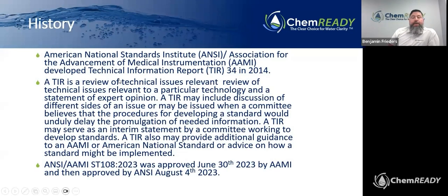So the history behind AAMI ST108 is ANSI and AAMI developed a technical information report, TIR 34, back in 2014. So this report and this information has been out for about 10 years. Here at GetChemREADY, we've been aware of TIR 34 for over 5 years now and advising customers and clients on how to implement these standards.